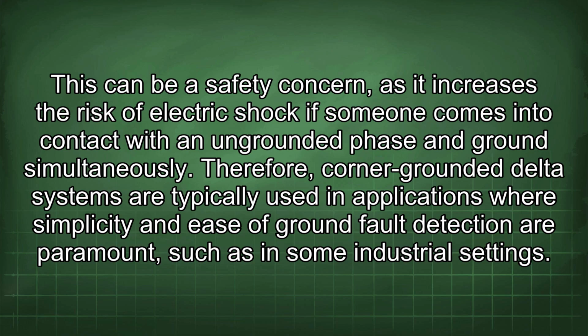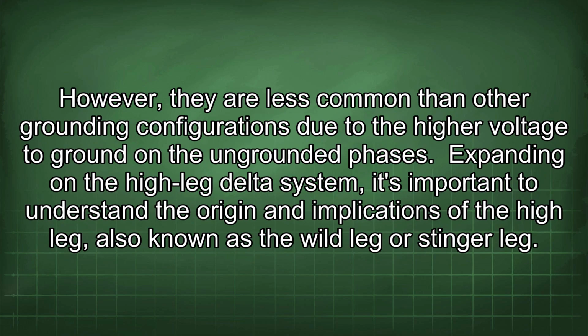Therefore, corner grounded delta systems are typically used in applications where simplicity and ease of ground fault detection are paramount, such as in some industrial settings. However, they are less common than other grounding configurations due to the higher voltage to ground on the ungrounded phases.